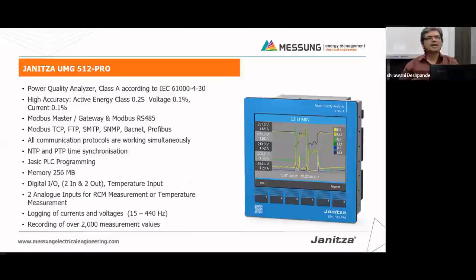This is a Class A product according to IEC 61000-4-30, as per Edition 3 of 2015, that qualifies as a Class A analyzer, and we are expecting customers to take benefit of this product. It is not wrong information that we are telling, but mandatory information going to be implemented by the Maharashtra Electricity Regulatory Commission and also by CEA, that you should have a Class A meter at your PCC. Recently in Mumbai itself, Adani Electricity has gone for a tender for almost 125 meters in their substations.